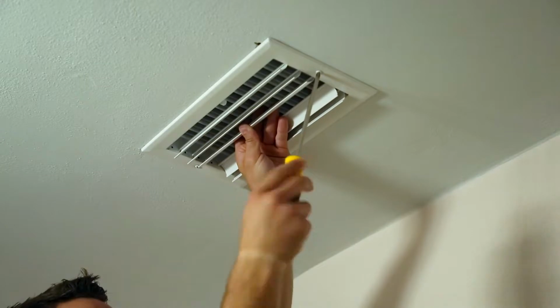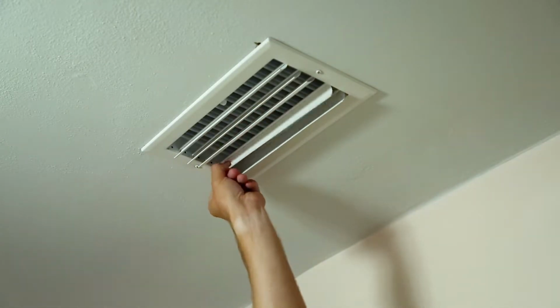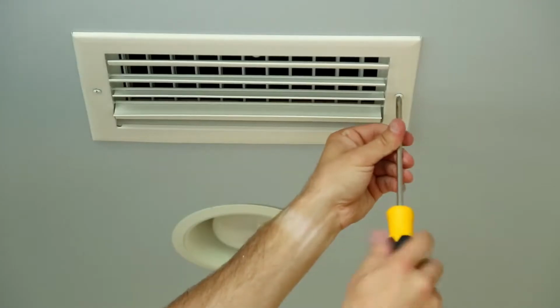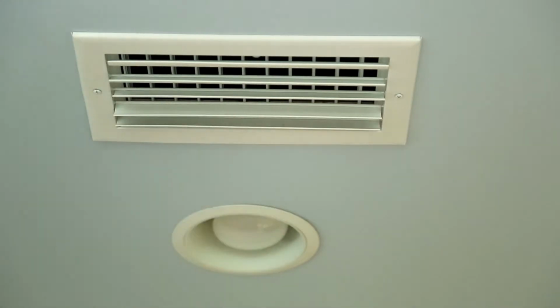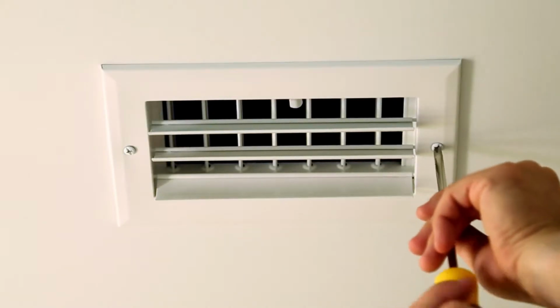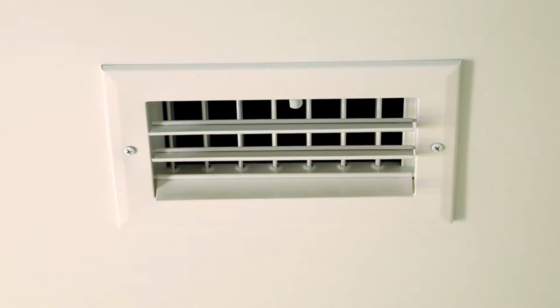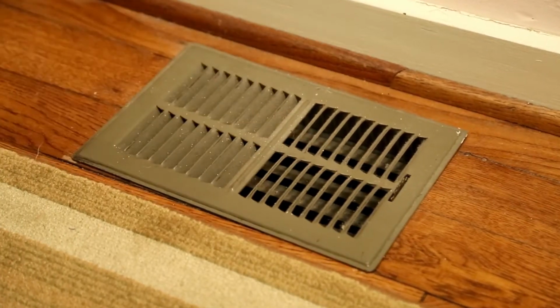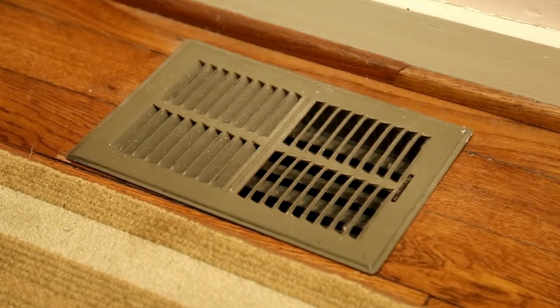Fresh air distribution registers should be located as far as possible from the ERV stale air registers. Install fresh air registers in the ceiling or on an interior wall 6 to 12 inches below the ceiling. If you must install the fresh air register in the floor, direct the airflow up the wall.